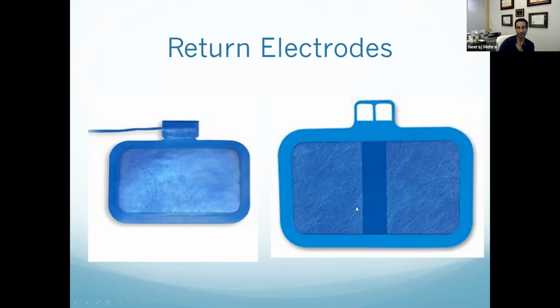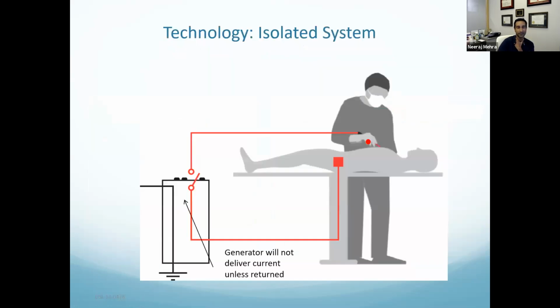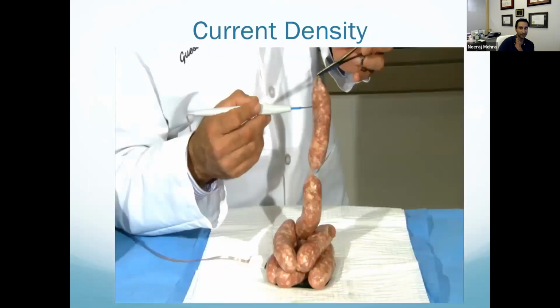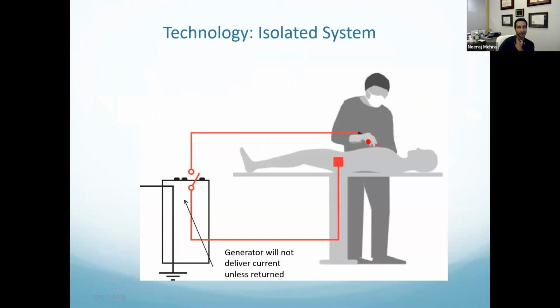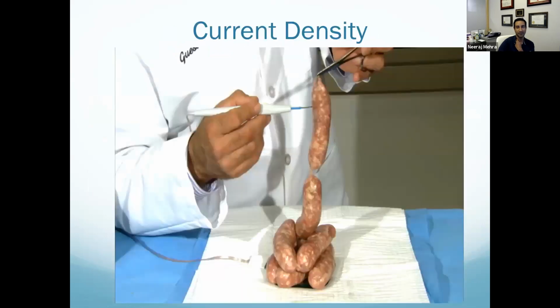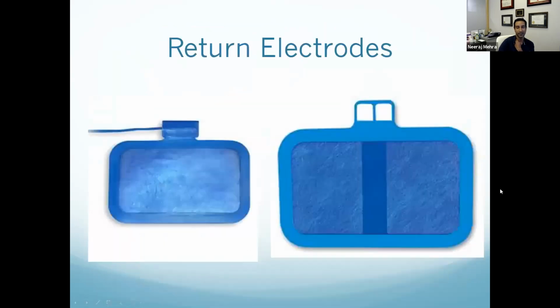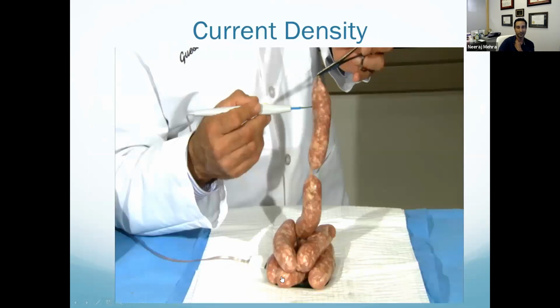And that's why if you see an error, it's because this thing isn't properly attached, because your generator has a safety mechanism built into it. Now, again, your generator only tells you the energy that's coming back. It's not telling you what's happening in between. So we have these pads that are safe, and they've helped a little bit. But here's an example where you can have your return electrode and have a burn in an area of high current density. I'm hoping this video works.